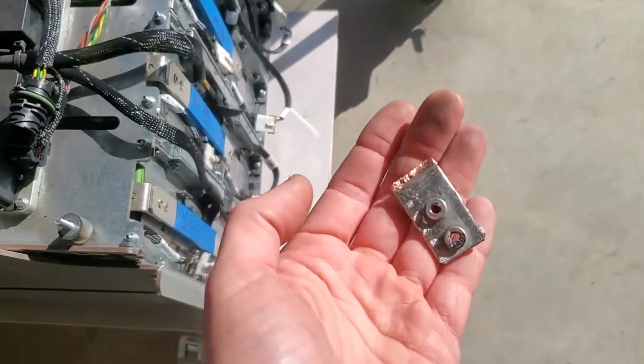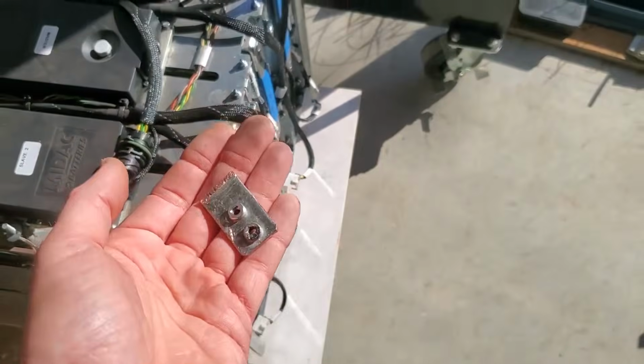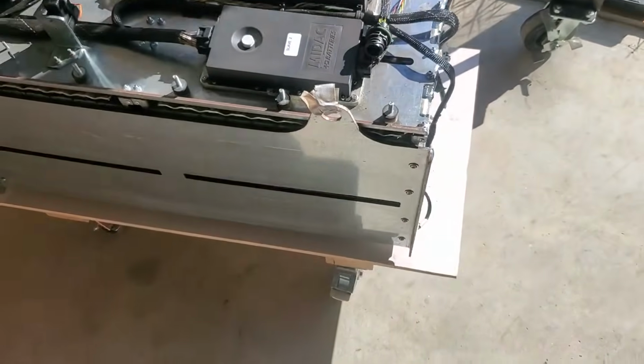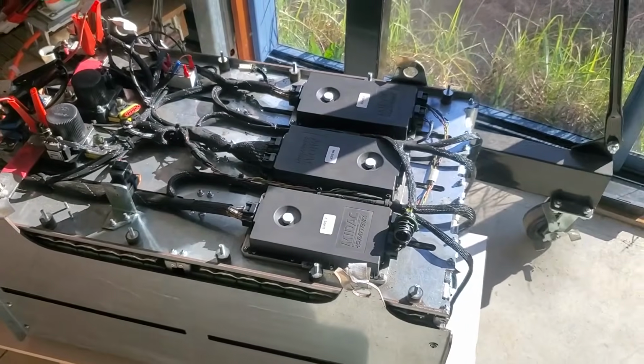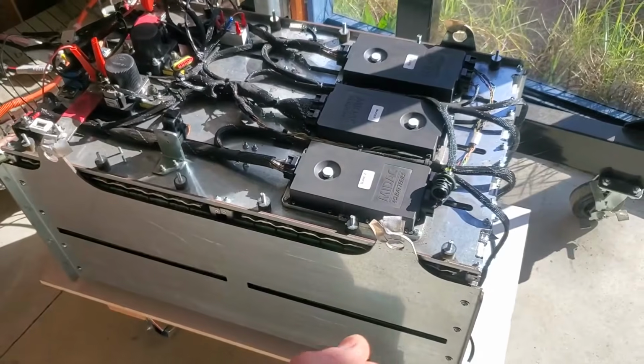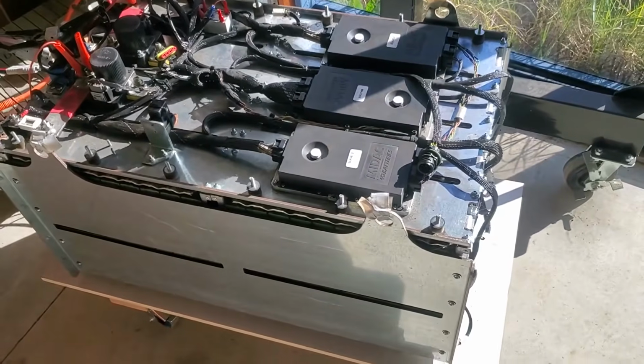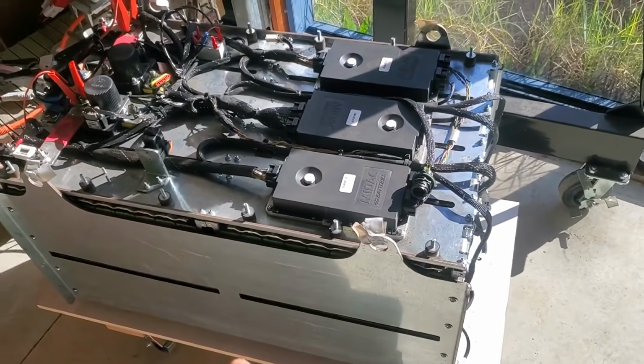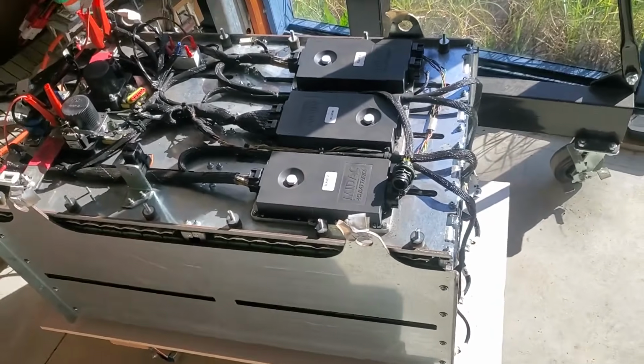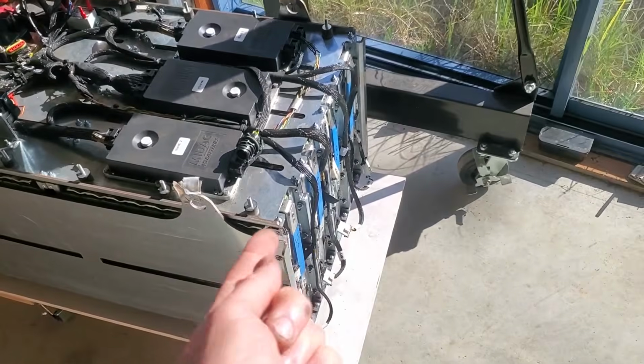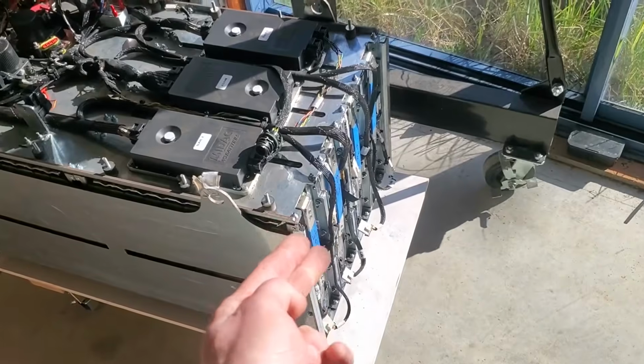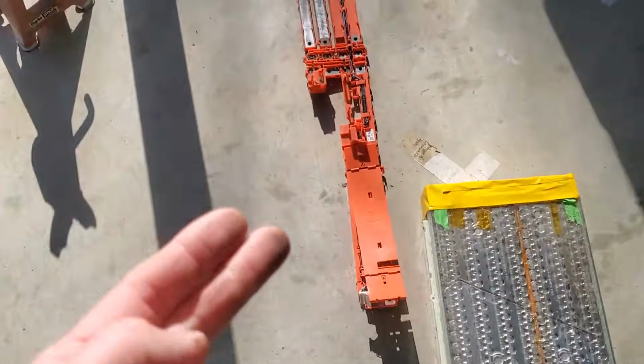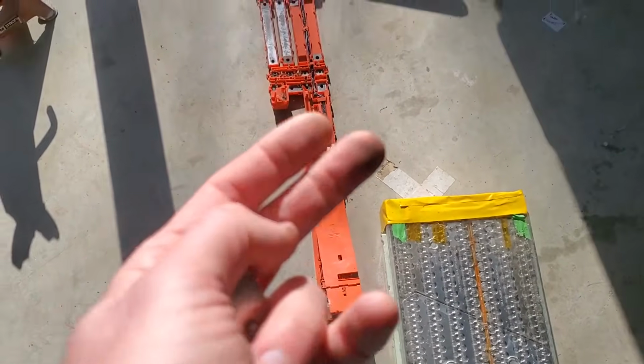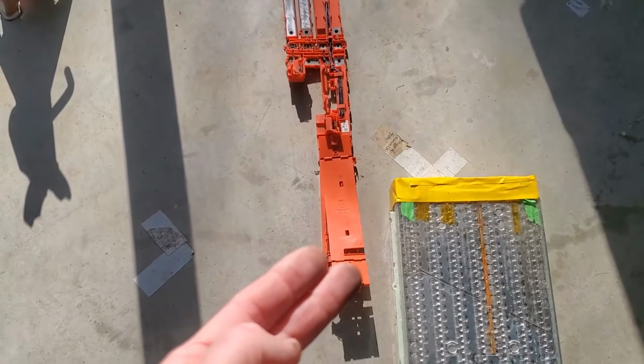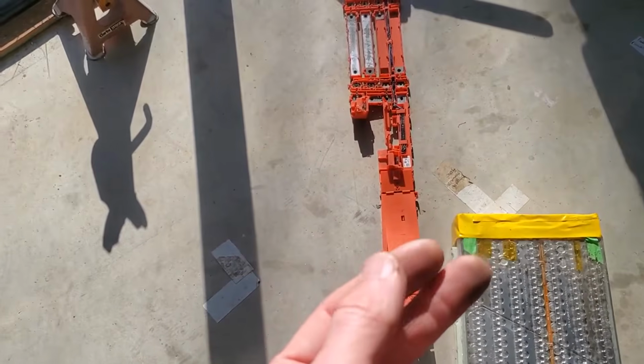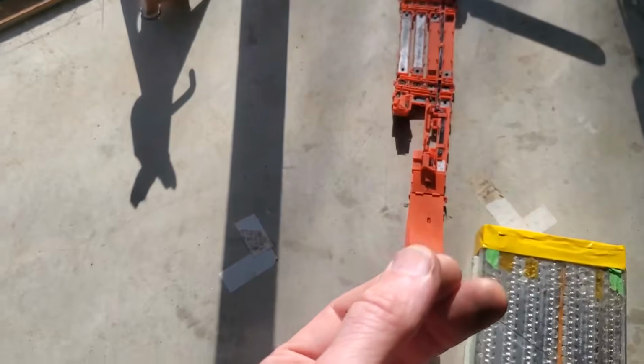So yeah, you get one short circuit or one contact to ground, that's fine sort of, but then any other follow-on fault causes basically catastrophe. And this battery has no mitigation, no design for that. They should have designed these sides to be strong enough to not swell, but they should also have put insulators behind the bus bars so that even if the swelling does happen, it won't cause a problem.